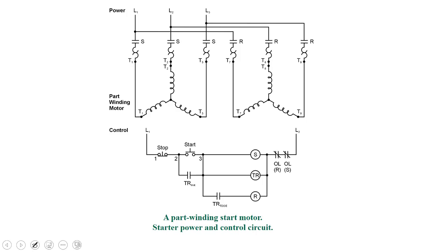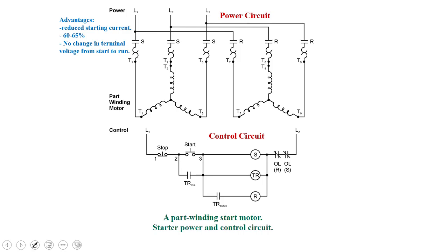So back to our part winding starter here, a little more about this. Some of the advantages of it: they reduce the starting current to that motor anywhere from 60 to 65%. That's what we're trying to achieve. No real change in terminal voltage from start to run. The disadvantages: they're a special order motor, perhaps, and 6 leads are required to run to the motor. So we have to run 6 wires instead of 3. And they have a really low starting torque. So they probably would not be suitable for any constant torque loads, more for just variable torque loads.